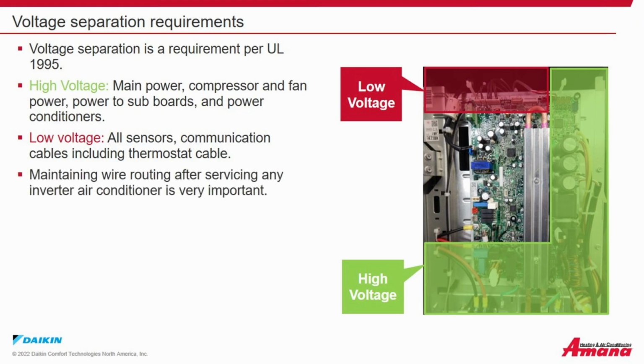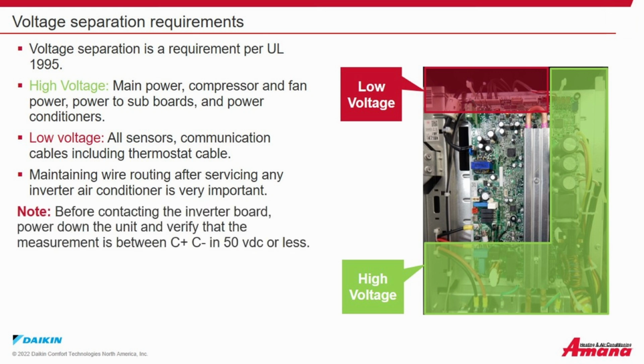Maintaining wire routing after servicing any inverter air conditioner is very important. Note, before contacting the inverter board, power the unit down and verify that the measurement between C positive and C negative is 50 volts DC or less.